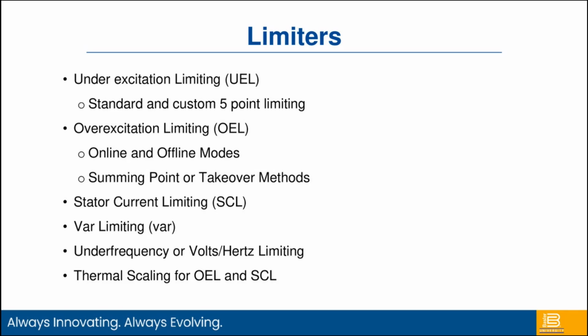Limiters are a prime example. We can do an under excitation limiter, an over excitation limiter, a stator current limiter, and an output VAR limiter, which may be a little confusing for anybody familiar with limiters. Typically, an under excitation limiter looks at reverse VARs, or VARs flowing into the machine. The VAR limiter in a DECS is actually output VARs. It's limiting the total amount of VARs flowing out of the machine, so it works a little closer to a stator current limit than an under excitation limiter. Both are looking at VARs.